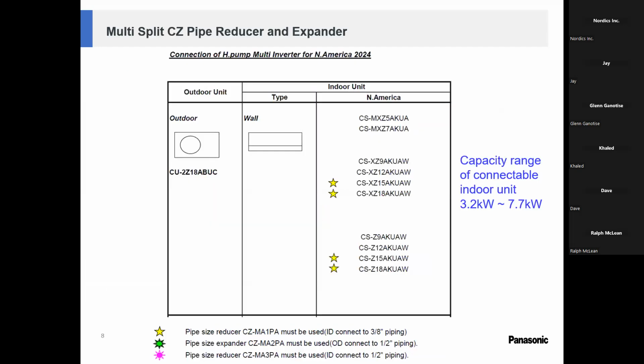So as you can see, at the very bottom, the pipe size reducer, we don't sell that product anymore. So you've got to get it locally from United Refrigeration, Nordics, or Wolseley, or any refrigeration air conditioning supplier. They do sell these adapters. I myself, we go and buy it from United. I'm not trying to promote United, but you can get it from any supplier, okay? And you will definitely need these adapters for an 18,000, for a 15,000, and for 24,000. I don't like putting 18 and 24 in a multi-zone application, but if you have to, you can go ahead and do that, but that's not my cup of tea.